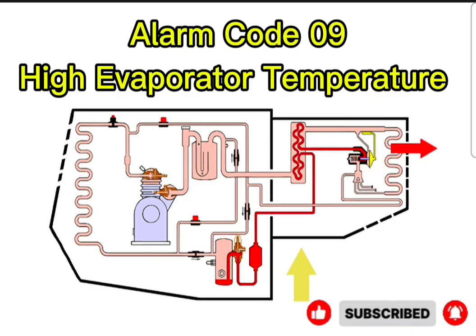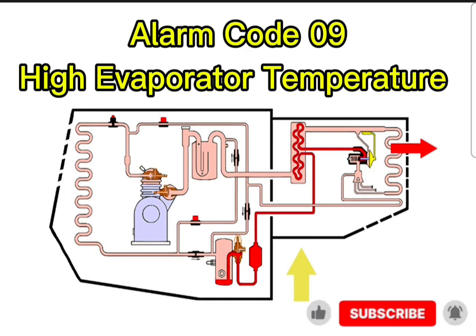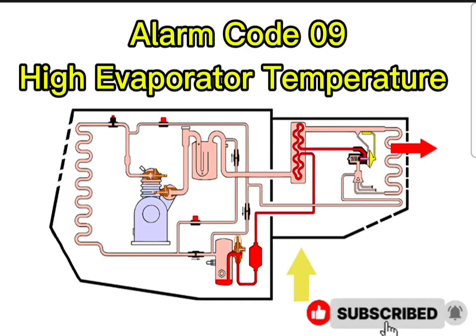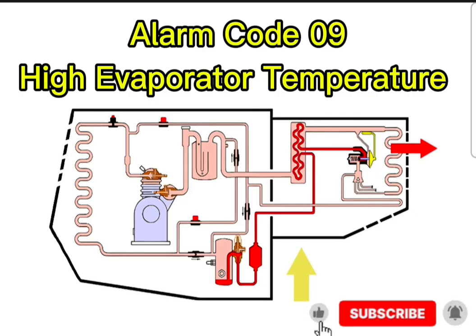Sure. So deep inside the cooling unit, you have the evaporator coils. That's the maze of metal tubes where the refrigerant actually absorbs the heat from the air inside the trailer. Okay, I can picture that. The suction header plate is essentially the main collection manifold. It's the junction point where all of those individual tubes merge back together to send the now warm refrigerant gas back to the compressor to get squeezed again. Okay, so it's the central nervous system junction for the heat transfer. It's the perfect place to take the system's core temperature.